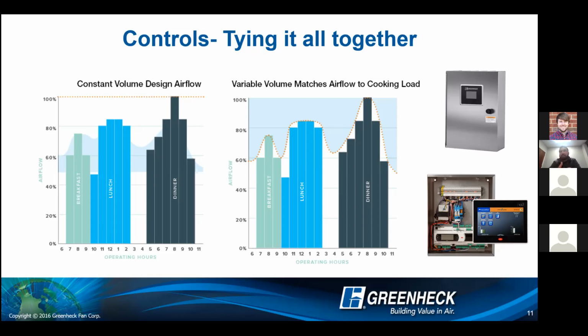It's going to provide a temp sensor. Greenheck puts our temp sensors in the actual exhaust cavity of the exhaust hood in order to sense temperature 5 times faster than the competition. But the code is going to require that when the kitchen is cooking or operating, when the appliances are on, both the exhaust fan and the makeup air fan need to be interlocked together in order to operate. So the way these control panels work is they're sensing temperature.